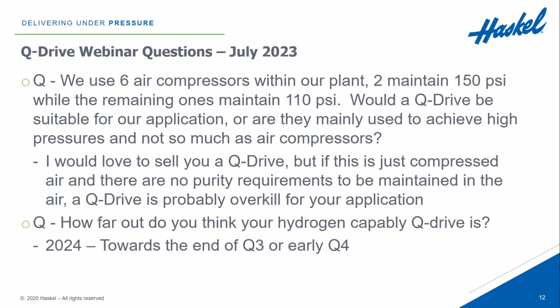We use 6 air compressors within our plant, 2 maintain 150 PSI, while the other ones are maintaining air at 110 PSI. Would a Q drive be suitable for our application, or are they mainly used to achieve high pressure and not so much as air compressors? I'd love to sell you a Q drive, but if this is just compressed air and there's no purity requirements to be maintained in the air, a Q drive is probably overkill for your application. Again, happy to talk to you about it, but I have a feeling that your current compressors might be, I won't say a better way to go, but I'm not sure with the Q drive. Other than the quietness, it may not bring you a whole lot of capability that you don't have from your current compressors.